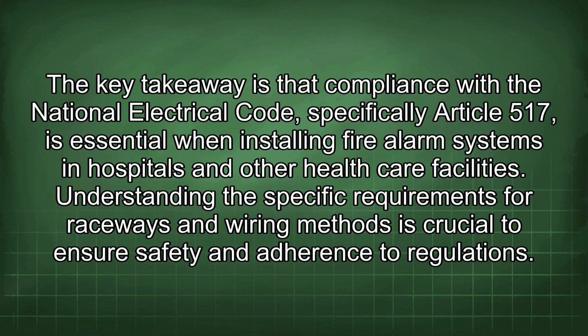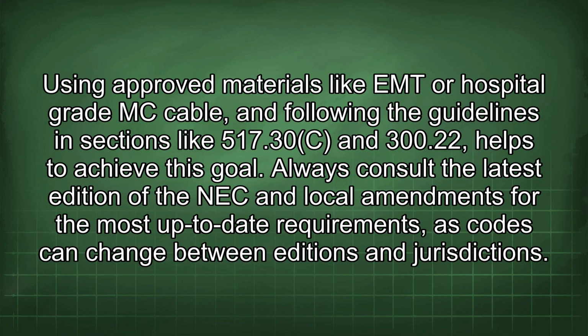517.30. The key takeaway is that compliance with the National Electrical Code, specifically Article 517, is essential when installing fire alarm systems in hospitals and other healthcare facilities. Understanding the specific requirements for raceways and wiring methods is crucial to ensure safety and adherence to regulations. Using approved materials like EMT or hospital-grade MC cable, and following the guidelines in sections like 517.30c and 300.22 helps to achieve this goal.